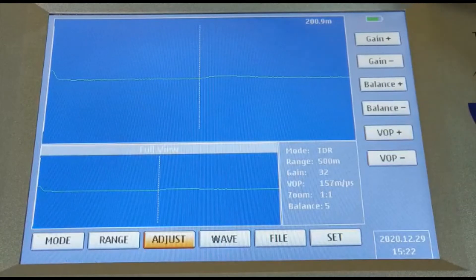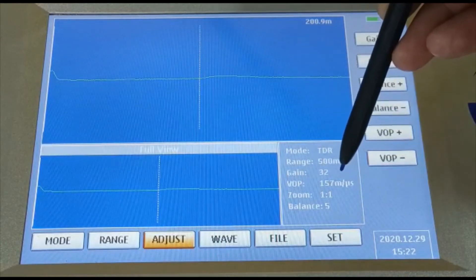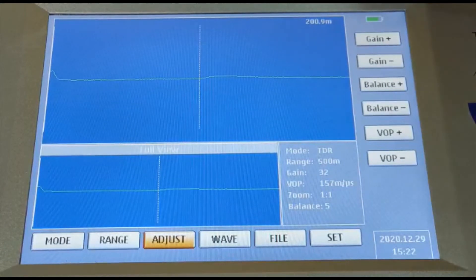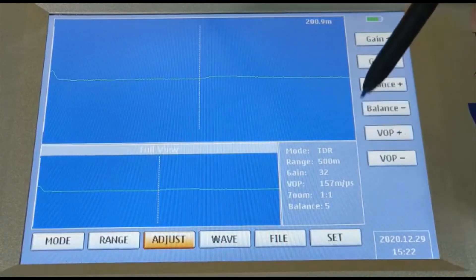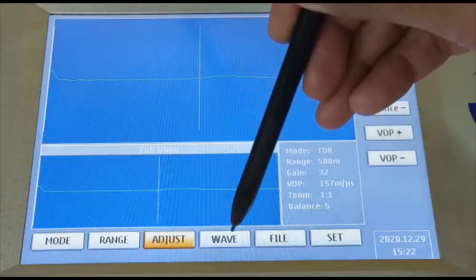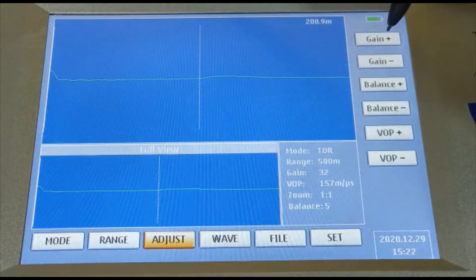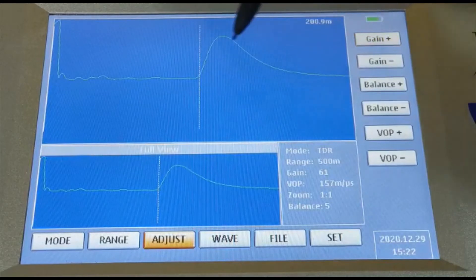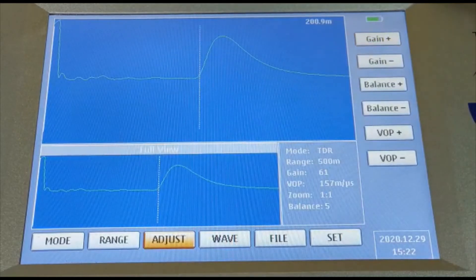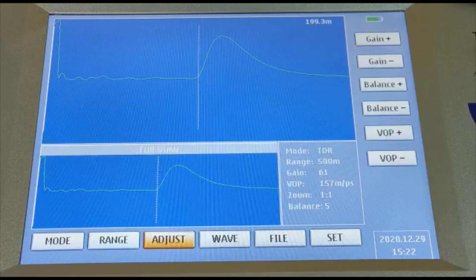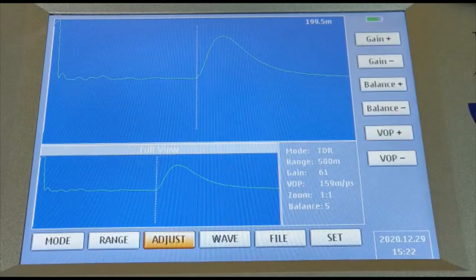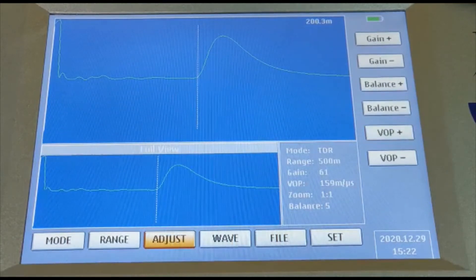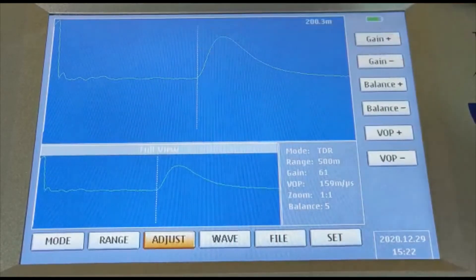Based on the cable insulation, my VOP is 157 meters per microsecond. Now let's increase the gain so that I can see the total end of the line. Go to adjust, increase the gain so that you can see the end of the line as an open circuit. This is our end of the line — I just press test and I get the distance to the fault.